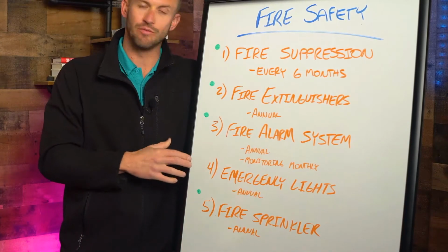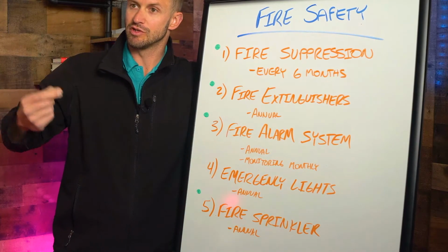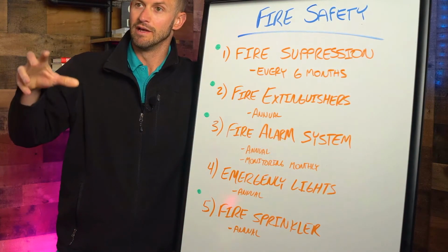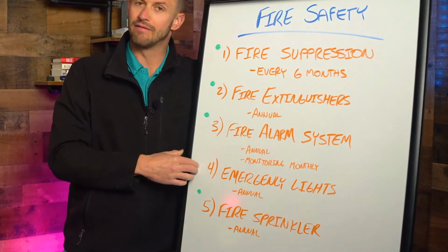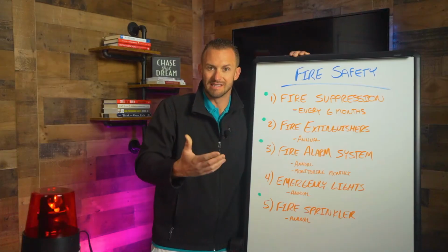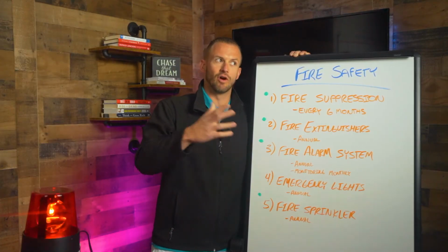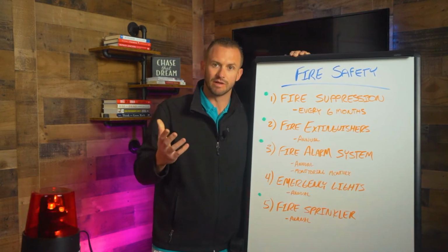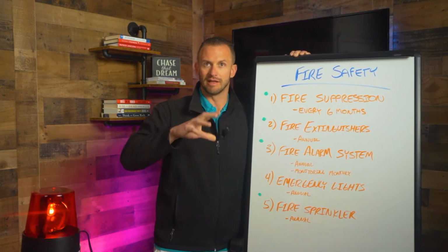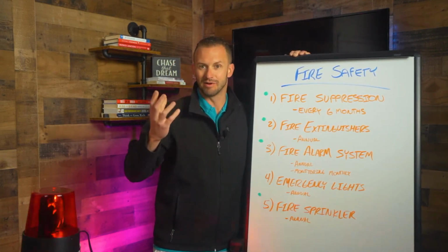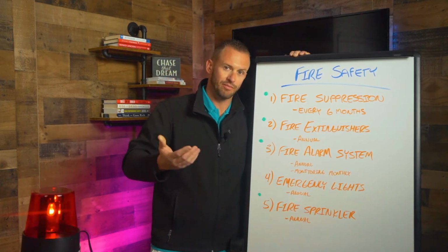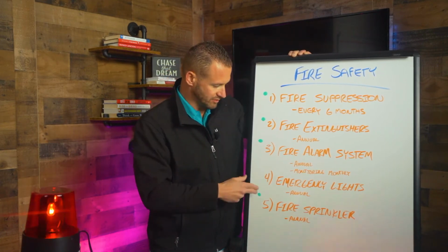The reality is that when you have your fire inspection, done annually by your local county officials, this will be part of their inspection. So you want to inspect it yourself at least annually: are all my emergency lights working, are my exit signs working, will all these lights come on if the power goes out, is a light burned out, is it a light problem, a battery problem, or a connection problem? Make sure you're checking that.